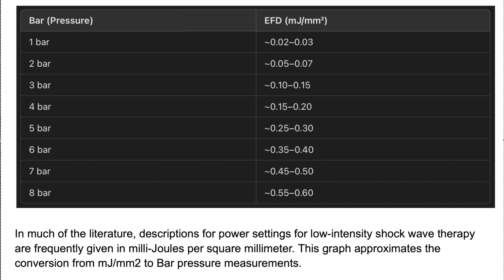These two actually measure different aspects of the shockwave. Bar pressure is kind of like, if you imagine a pond, the size of the stone you throw tells how strong the impact is when the stone hits the water. Energy flux density is measuring how much energy spreads out from the splash across the ripples.